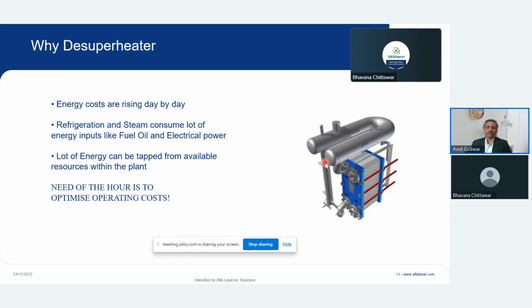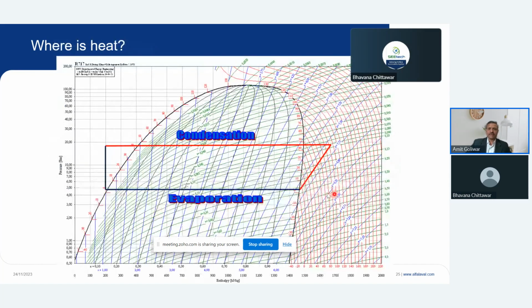Then many plants also have ammonia used as a refrigerant, and this ammonia refrigeration has an opportunity wherein, due to a property of the refrigerant, it goes into a superheated zone. After evaporation, when it goes to the superheated zone, you can again generate hot water there. The current practice is that it is lost in the condenser. So instead of losing that heat, we can utilize it to generate hot water again. Ammonia refrigeration is typically used in chemical plants and the food industry, wherein this hot water can be very well utilized for CIP and boiler feed water.